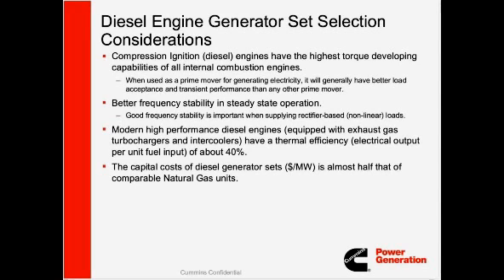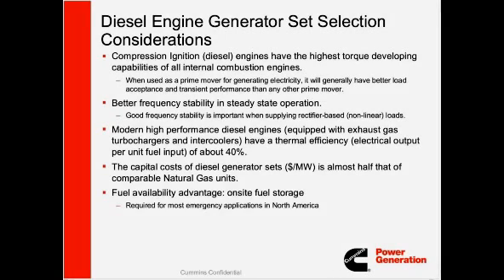The capital cost of diesel generator sets in dollars per megawatt is much, much lower than that for comparable natural gas units, and in many cases, it could be as low as half of that for natural gas units. This is not the operational cost, but this is basically the purchasing cost of this equipment and the packaging of these units. Fuel availability advantages also make diesel a better solution for standby applications. This is required by many authorities having jurisdiction for emergency applications. They need on-site fuel storage, and many inspectors will not accept natural gas gensets as the emergency power supply system.